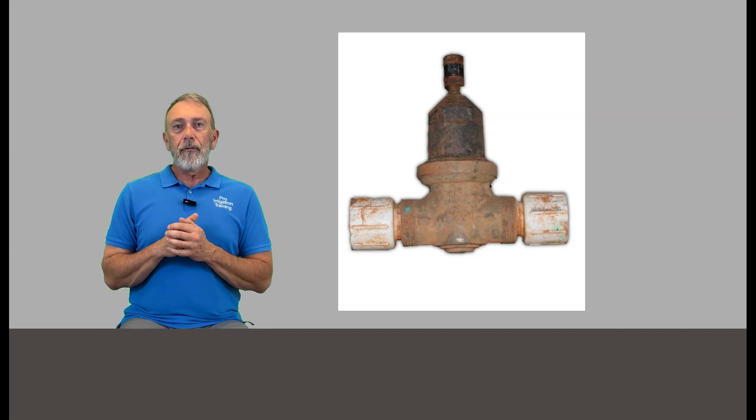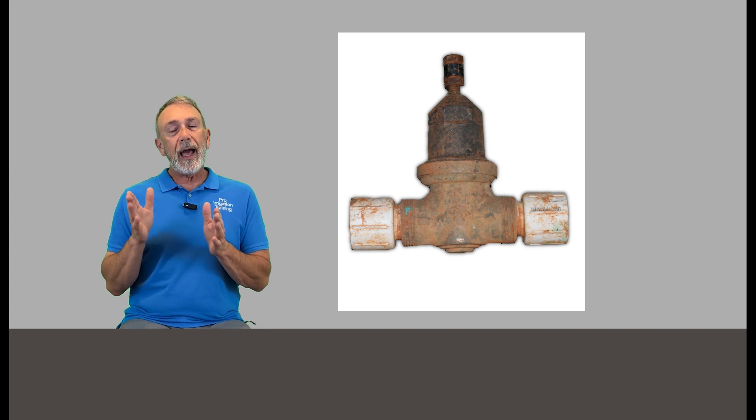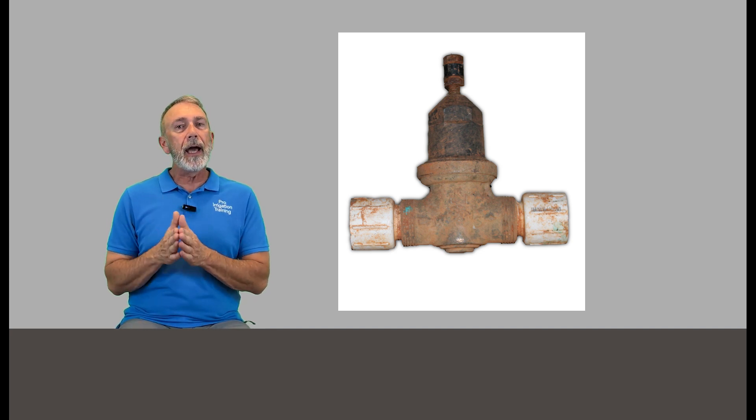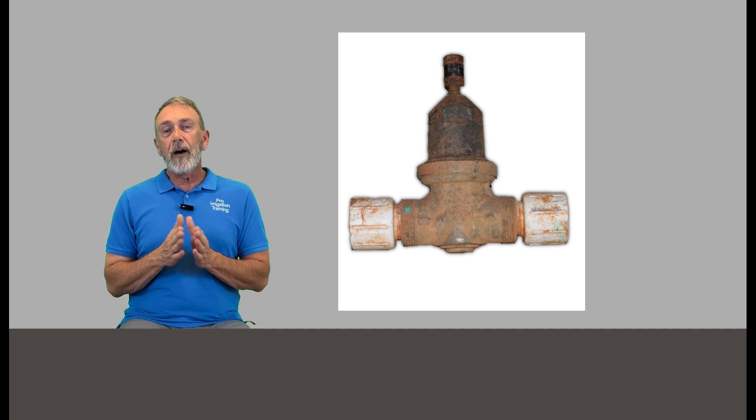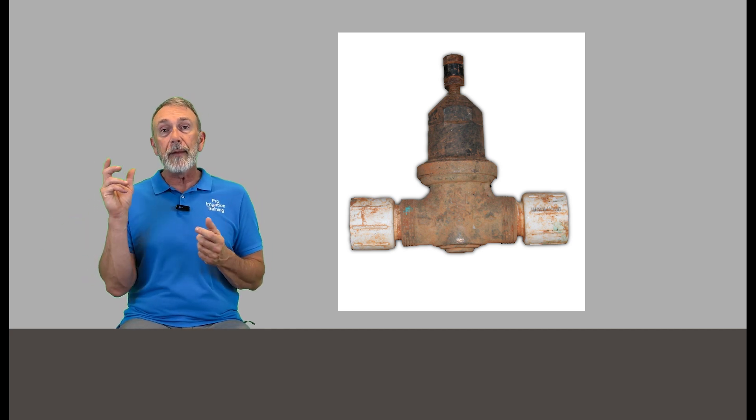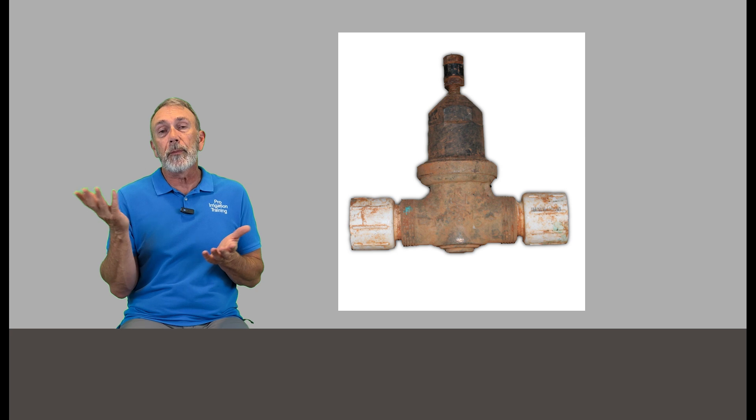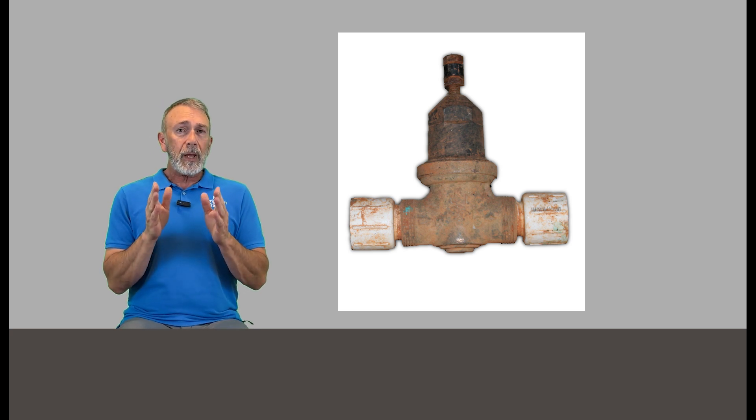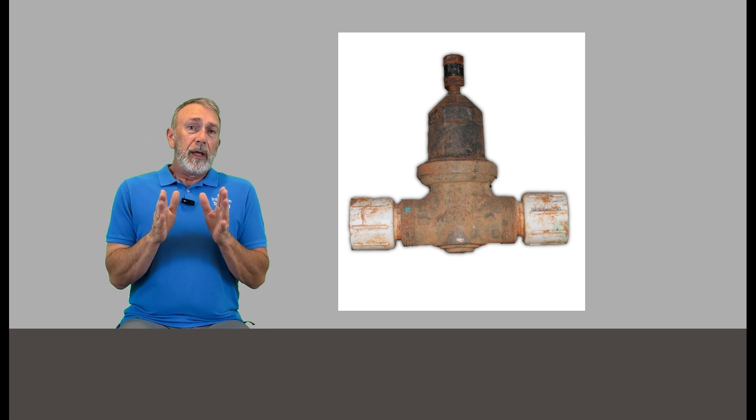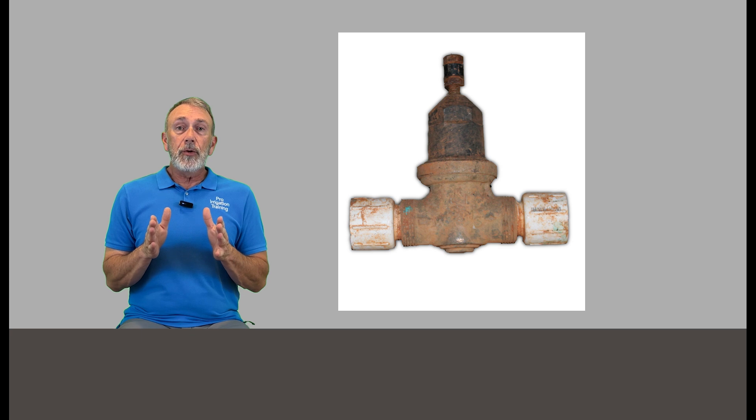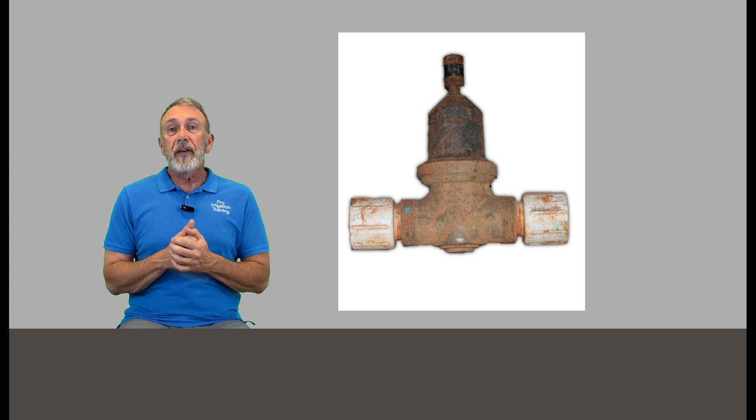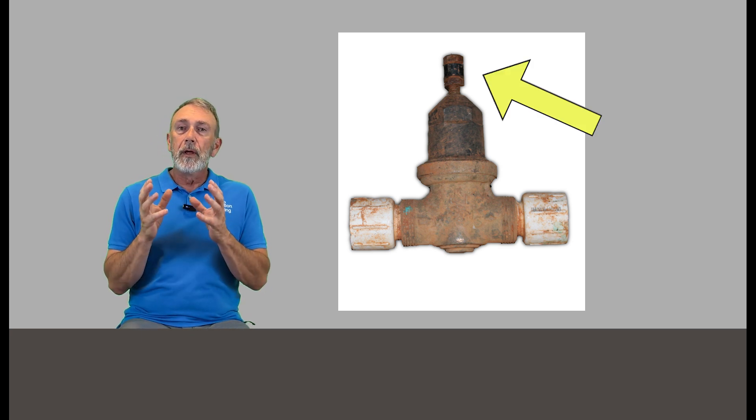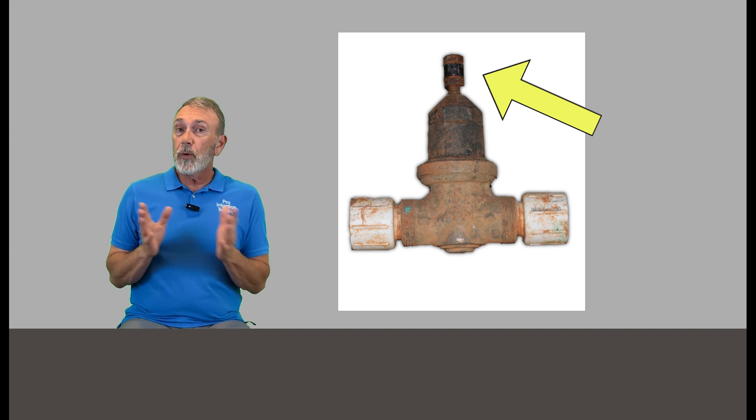Now do we have a pressure reducing valve in play? These are harder to check unless you have a hose bib or a hydrant or something that's downstream of this device on the main line that you could put a pressure gauge on and just check what the pressure is. But in the absence of that, what we're going to have to do is just open it up fully and see if that affects the situation.